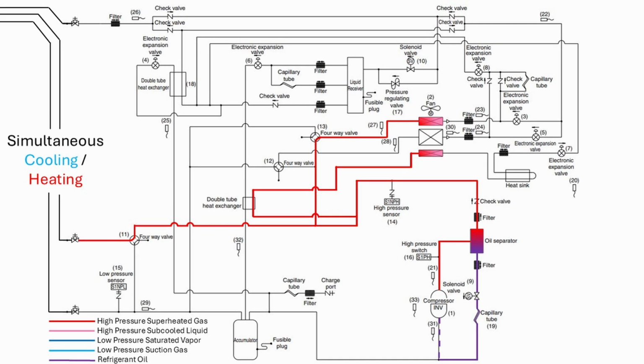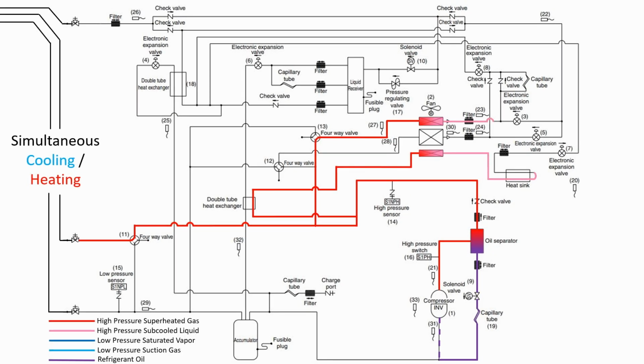The liquid refrigerant leaving the smaller section of the outdoor heat exchanger travels through the heat sink to cool the inverter board. The liquid refrigerant leaving the upper section of the heat exchanger and the liquid refrigerant leaving the heat sink both travel through an electronic expansion valve. The expansion valves are not metering the refrigerant, but controlling the flow through the outdoor coils to get the perfect amount of subcooling.